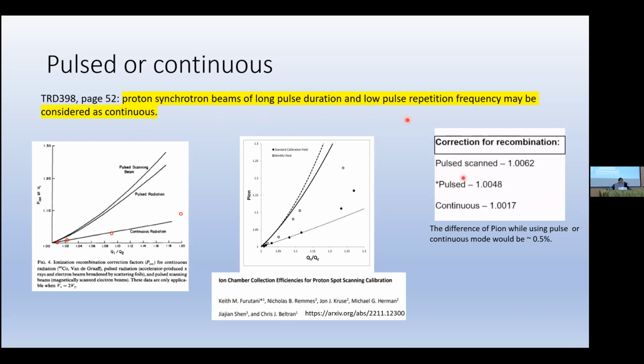This comes in when you're doing this calibration, you have something called continuous. Now, I'm not talking about how you're treating the patient, but you have continuous radiation, pulsed radiation, or a mixture. And depending on how you calibrate, part of this you have to take into account in your quality factor when you're correcting for that M_raw. There are differences, and this is kind of vague. I again put out the synchrotron. But when you actually do measurements and do things different ways, you can see that the statement made there is not necessarily right. And if you just follow that, again, you might be 0.5% off.